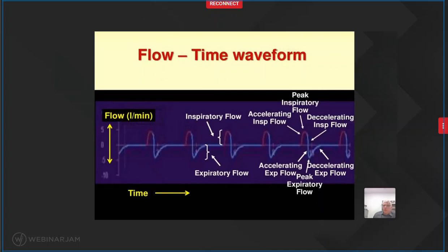So one of the most important waveforms, at least to me, is the flow time waveform. The flow time waveform is a bit more complex because it has a positive element and a negative element. Anything above the baseline, positive, means flow going into the lungs. Anything on the bottom, going negative, is flow that goes away from the lungs. So this flow time waveform has an inspiratory flow that has two components. One is the accelerating inspiratory flow, the initial inspiratory flow that the machine will deliver to try to achieve the volume or the pressure, depending on what type of ventilator you're using. And then as the lungs start expanding and filling with air, the flow will start slowing down, and that's the decelerating inspiratory flow.